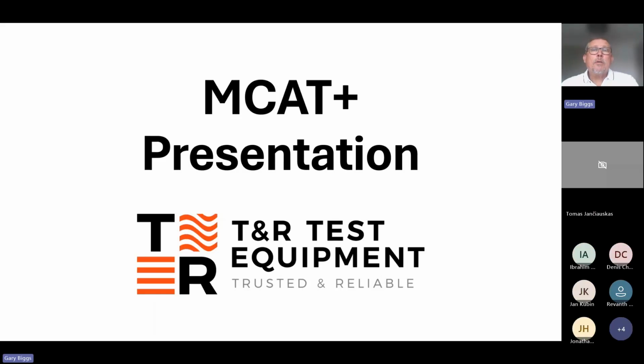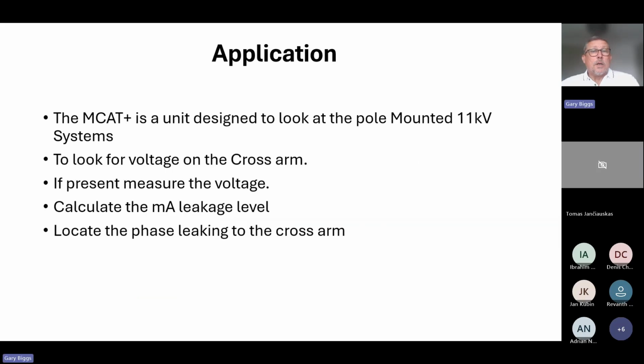MCAT stands for Micro Cross Arm Tester. And that's exactly what the product's about. It's about looking for leaky insulators on 11 kV systems, and identifying (A) if you've got a leaky insulator, and (B) how to locate it. So as I said, that's the whole idea of this product, to look at 11 kV pole mounted systems.